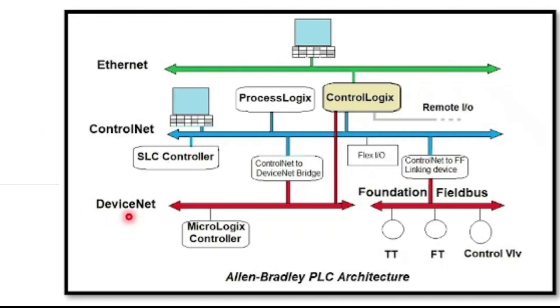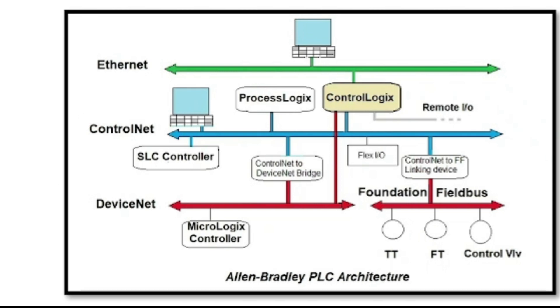DeviceNet is an open, low-level connection link that connects simple process measurement devices like sensors and actuators. It is the lowest level of communication, getting data directly from the field. The ControlLogix controller can also get data via a wired fieldbus foundation directly from the field, and from ControlNet we can gather data from all those networks, provided the required modules are in place.